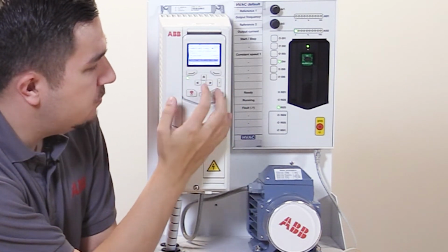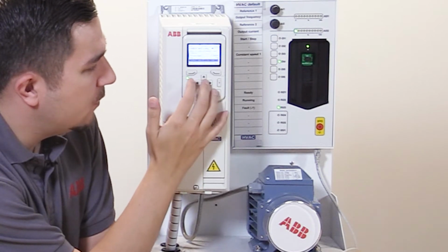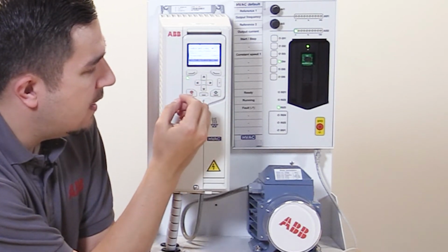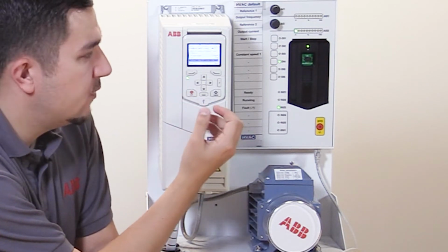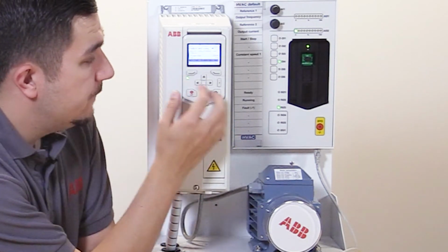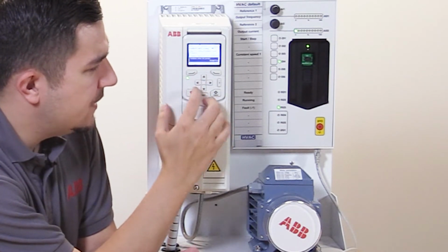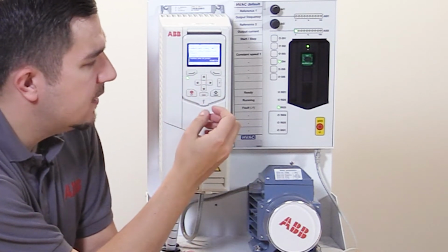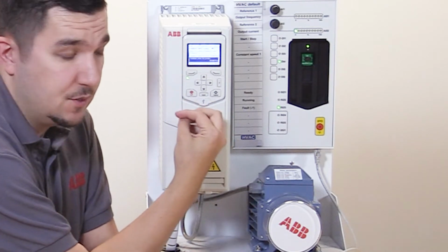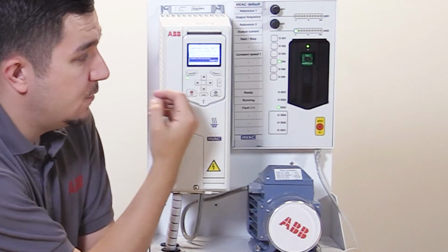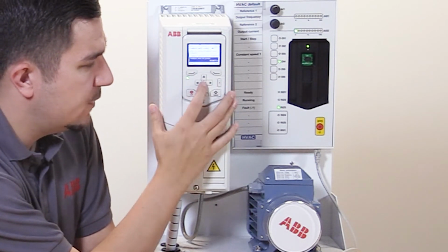Once we've looked at the units, we've then got what the feedback is. So this is defining what our 4 milliamps would equate to in terms of temperature. We're going to set that as 0 degrees Celsius, and in this case what our maximum would be, our feedback when analog input 2 is at its maximum. So this is the maximum range of the temperature sensor, which I've put as 50 degrees.